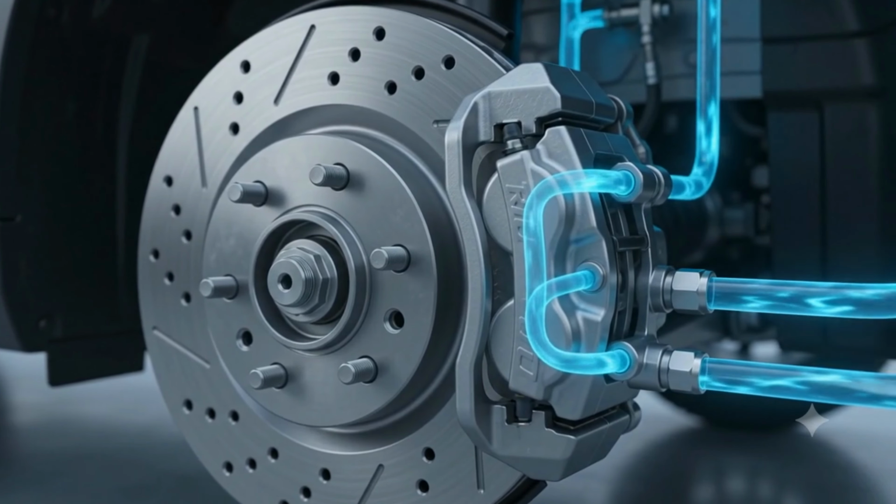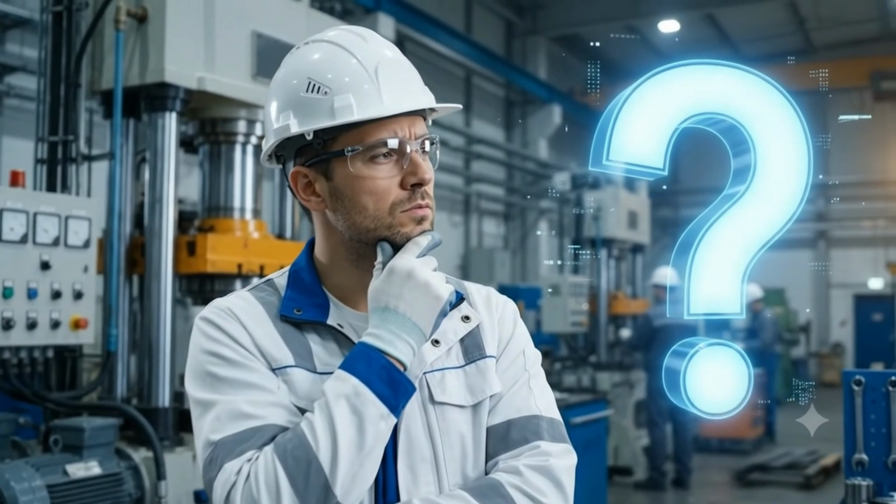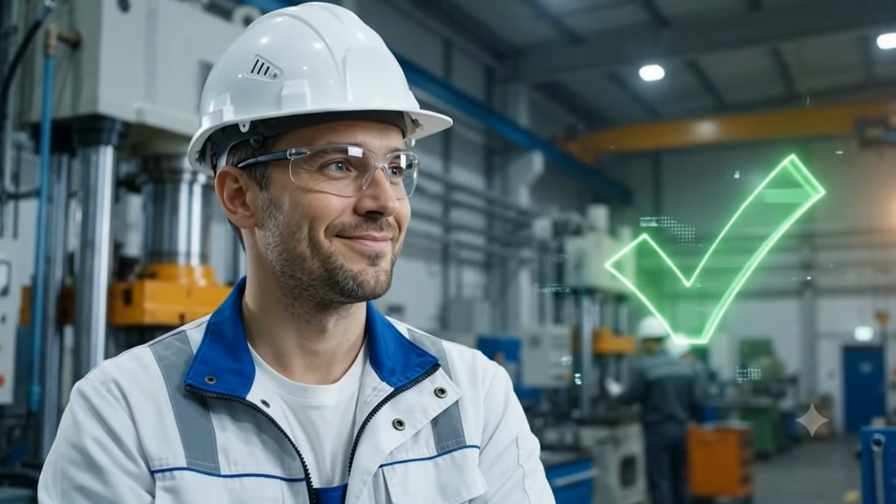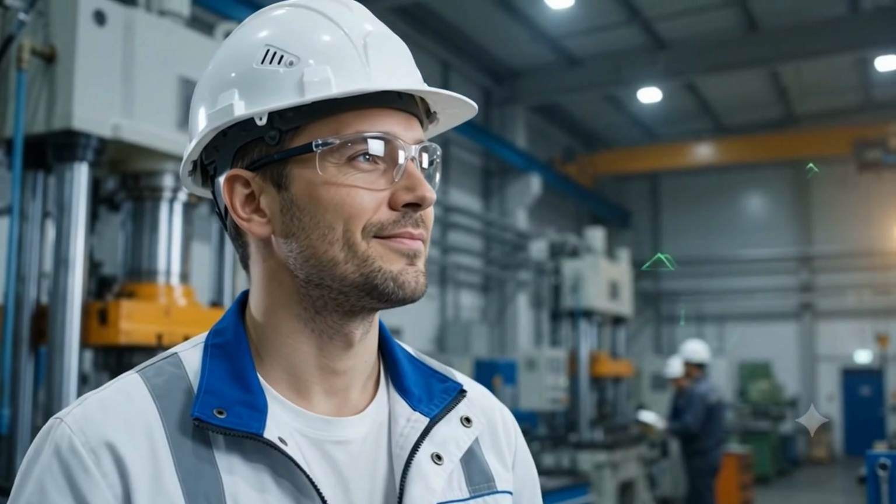Troubleshooting logic number 2. Flow versus pressure. When troubleshooting, you must understand this fundamental truth. A pump does not create pressure. A pump only creates a fluid flow. Pressure is only created when there is resistance against that flow. In a system, this resistance is the actual work or the operational purpose you are trying to achieve. Remember this, pressure only builds when work is actively being done.